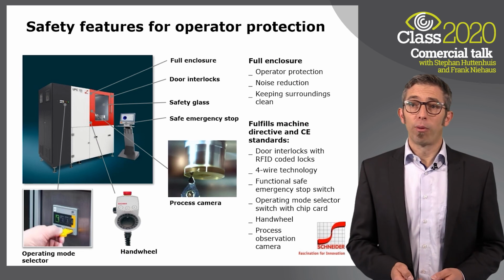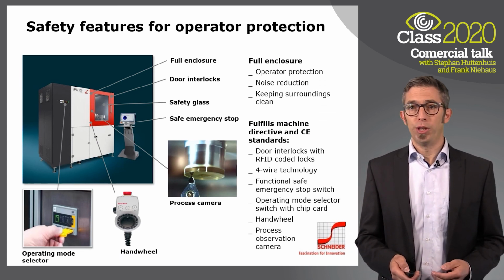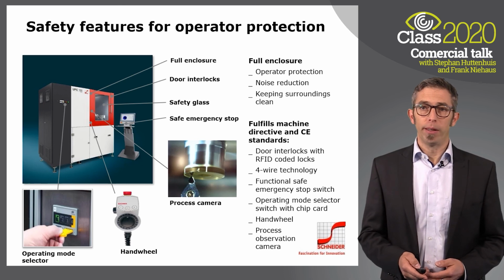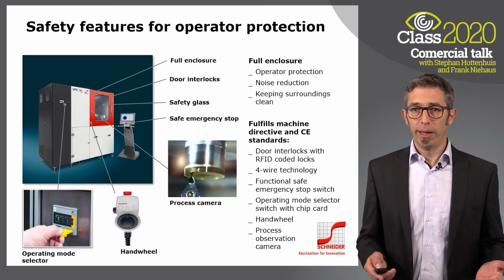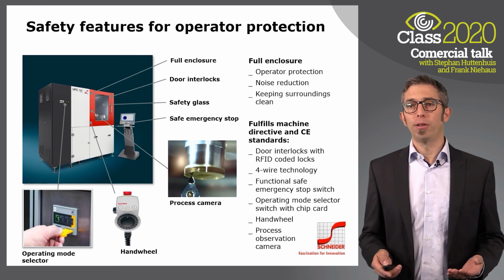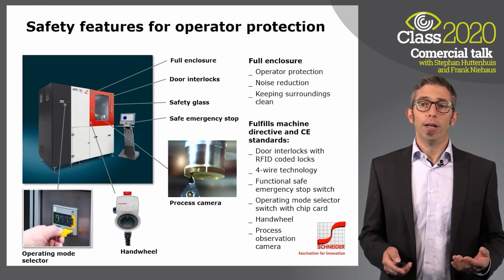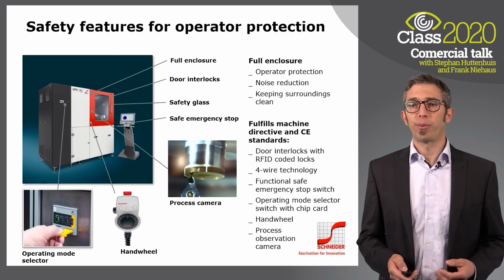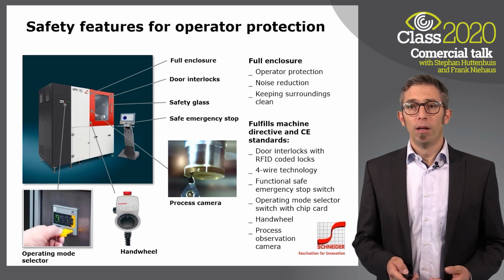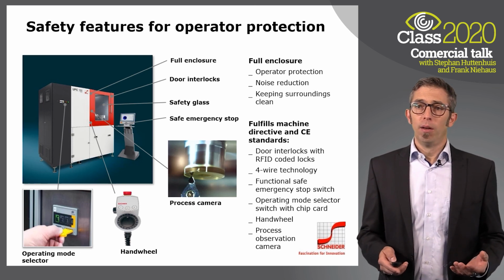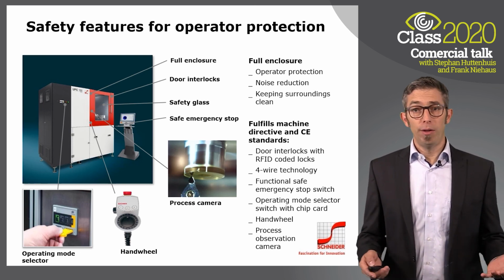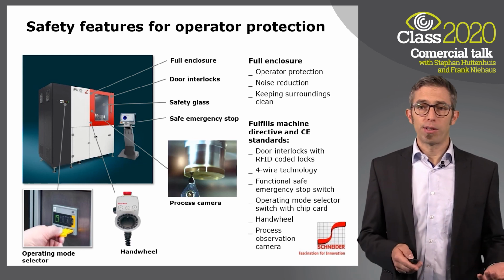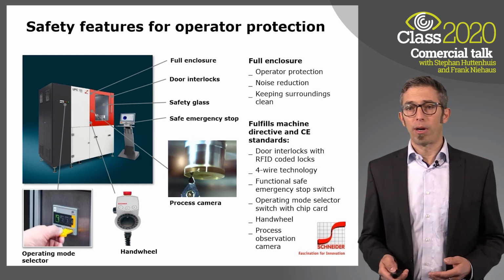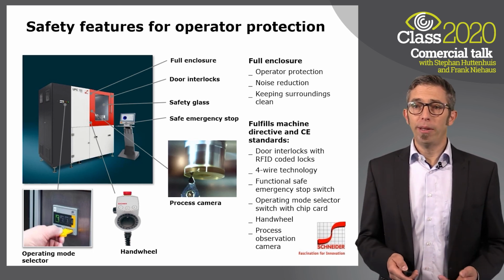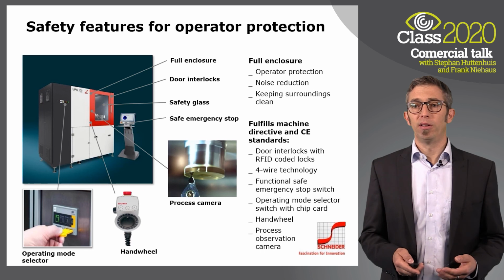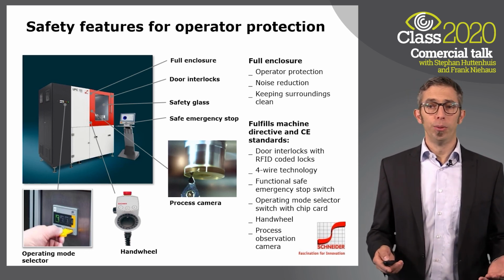Last but not least, I would like to come back to the outside shell of the machine and the integrated safety aspects. The full enclosure protects the operator, reduces noise and contamination of the surroundings in the lab, but it is also required to fulfill the regulations regarding safety for machine tools. This is not only achieved by the housing, but by a number of different measures like safety glass, door interlocks, functional safe emergency stop buttons, process camera, and so on. Hence, many things that ensure a safe operation of the machine and of course protecting you and your staff in the laboratory.